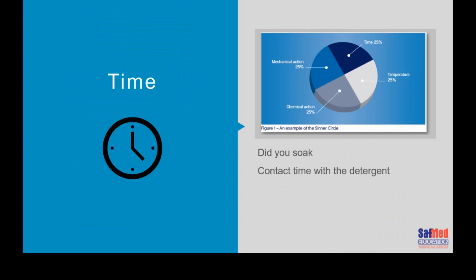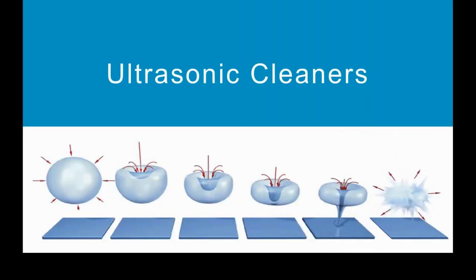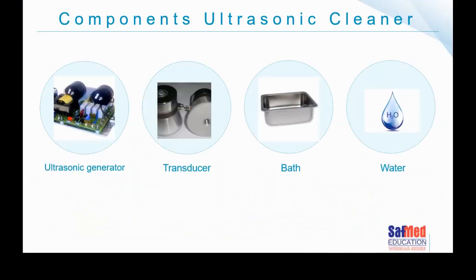And then the last aspect of the Sinner's Circle to take into cognizance is the time. You need contact time with the detergent, with the water, with the mechanical action. If you think about it, if you go to the hairdresser, you've had your hair washed, and afterwards they apply the conditioner and then they massage your scalp, which is lovely because it helps for hair growth. But all of that massaging allows the conditioner time to do its job. So the chemicals need time to interact with the device for cleaning efficacy. So it's in a circle: chemical action, mechanical action, time, and temperature. Those are the 4 components that can help us make sure that we're cleaning our instruments correctly. If we apply those 4 aspects, we should hopefully come up with a clean instrument.